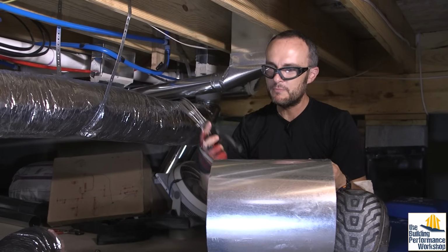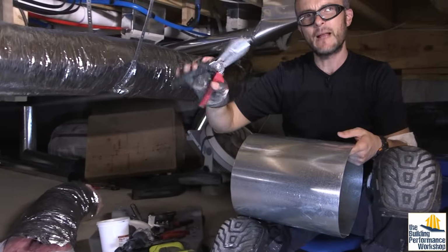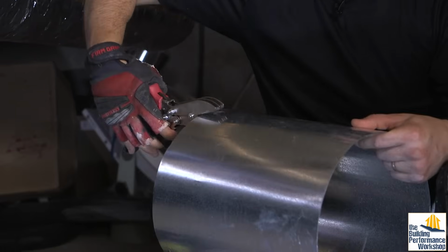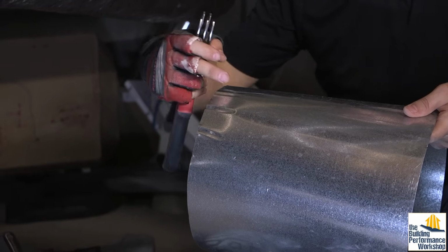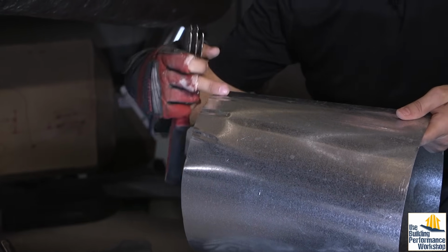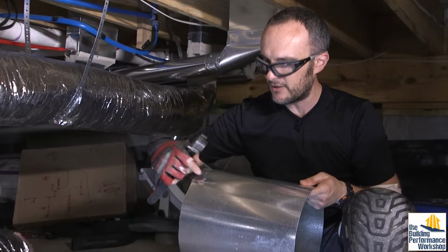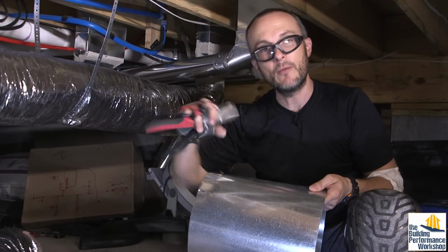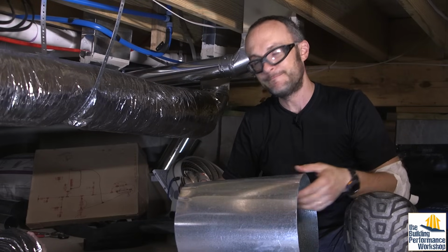But these things are super easy to use. I always go full depth. There are a couple different sizes of this, but I find that the further I can stick this thing into the next duct and then screw it together, the easier it is. And you'll see that machined ones are going to be ribbed the whole way down. In real life, you don't need to do every single one. You can do it a couple inches apart like this, and it'll still be small enough to fit inside an end that's uncrimped like this one is.